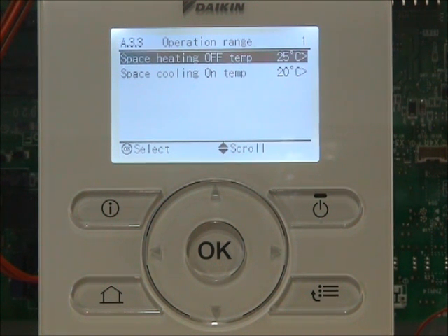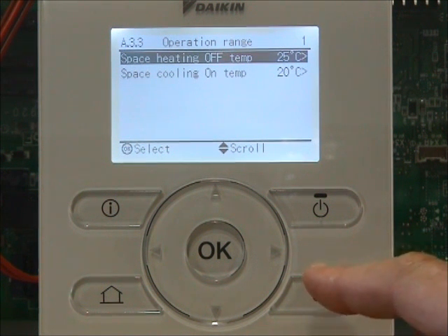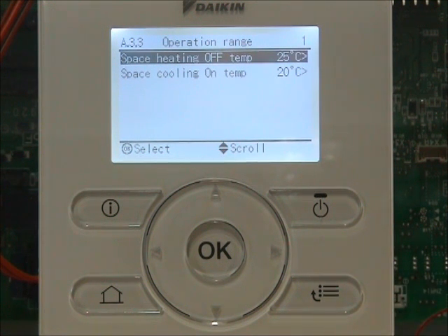The upper limit on the single fan outdoor unit size 4 to 8 is 25 degrees, and on the 11, 14 and 16 it is 35 degrees. Hot water temperature is much higher.